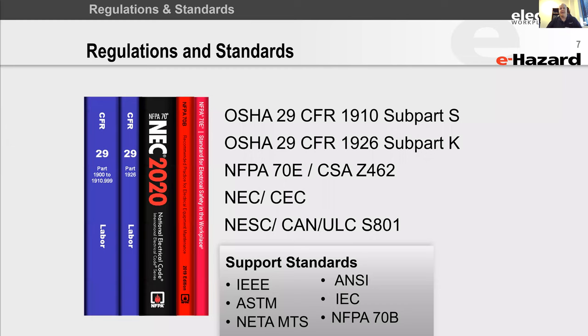So for the most part, how we're going to mitigate the human error piece is by removing the hazard. When we look at turning the power off—well, it's more than that—in 70E we define the term 'establishing an electrically safe work condition.' That means we've de-energized the equipment, locked it out in accordance with established standards, and verified it's in a zero energy state.